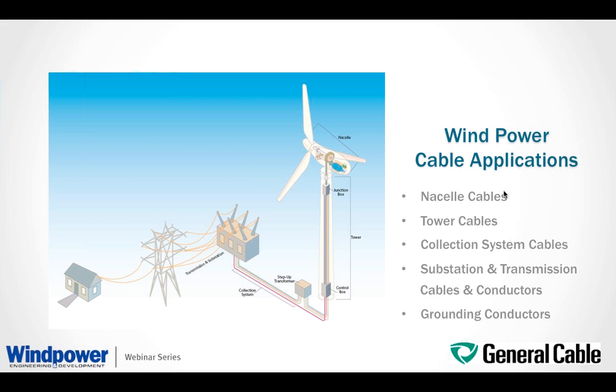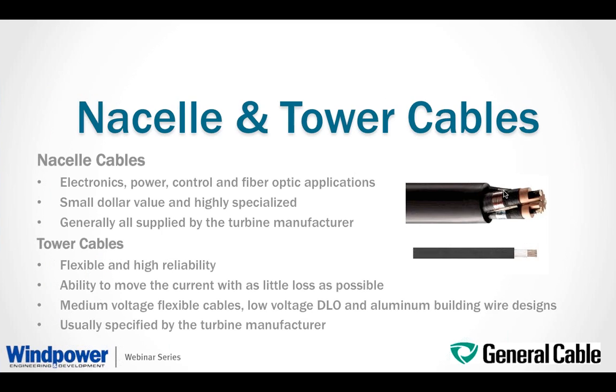Here's an illustration showing the different applications in a wind farm where various wiring and cable constructions are used. There are a number of cable designs used, starting in the nacelle, then the tower, and then the collection system. There are also substation and transmission cables and conductors, as well as grounding conductors. In this presentation, we'll pay particular attention to the medium voltage design used in the collector system.